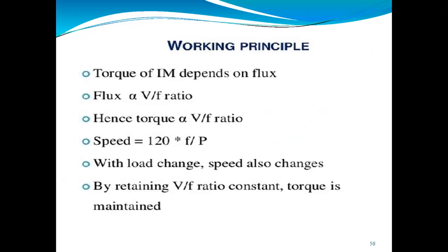At that time we are supposed to maintain the V by F ratio constant, and as we are maintaining it, flux will be proportional to voltage and inversely proportional to frequency. So if we keep this ratio constant, flux will become constant.